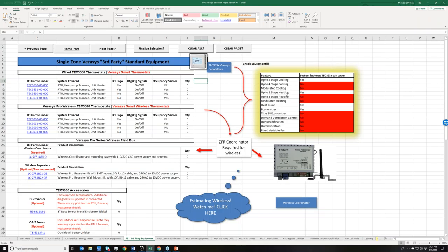All you have to do when you're looking at existing equipment is ask yourself: do I have anything more than 2 stages of cooling, anything more than 2 stages of heating? If not, great, we're in the clear. If I have any sort of modulated cooling or heating, the TEC thermostat is not a solution - we cannot integrate it using this device into Verasys.